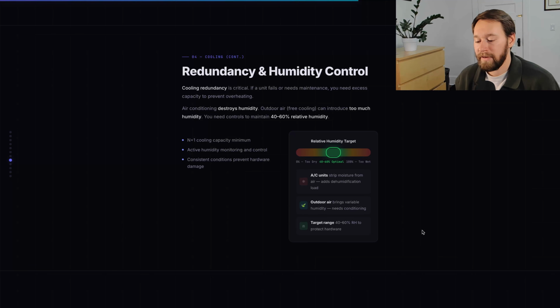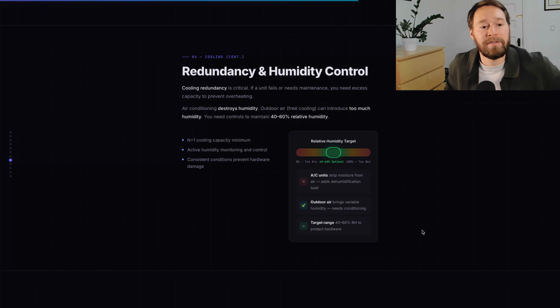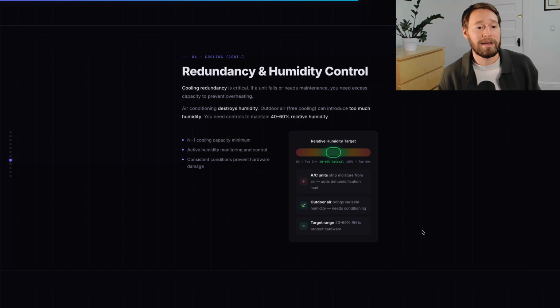The final component to cooling is humidity. If you're running a lot of air conditioners, you're pulling a ton of moisture out of the air. In a data center, you don't want super low humidity, and you don't want super high humidity either, so there's a sweet spot that needs to be maintained. If you're not buying a typical data center air conditioning unit, there are going to be no controls built in, and you'll have to do this with your own controls. This could be as simple as humidifiers that turn on when humidity gets too low, and dehumidifiers that turn on when it gets too high. But if you fire all this up and humidity is at 5%, you're at risk of creating a big static shock that could destroy a ton of hardware. That's how you want to look at redundancy around your cooling systems.